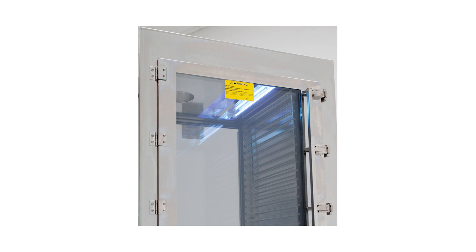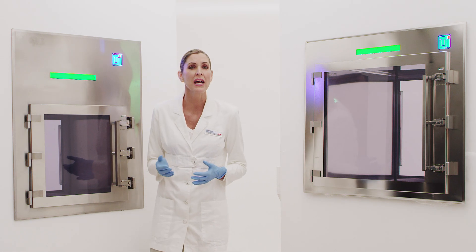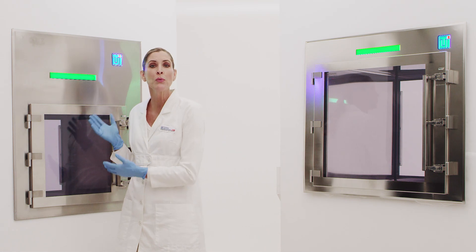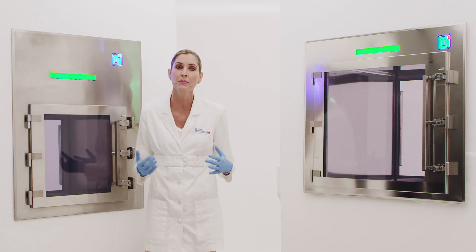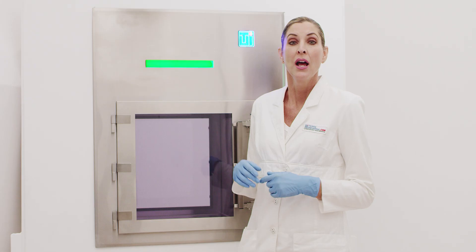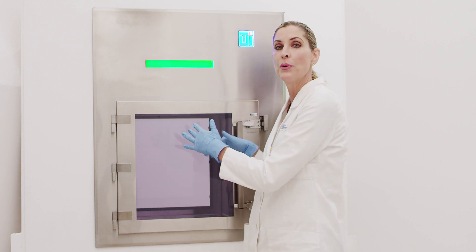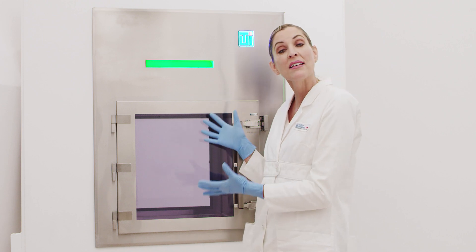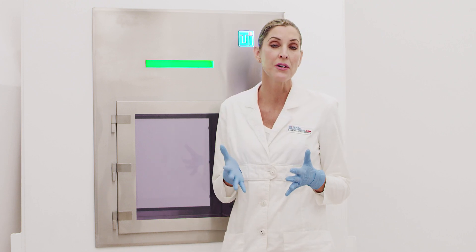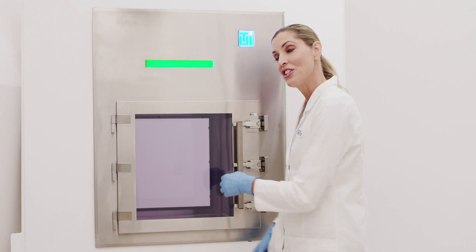The UV light automatically shuts off when either door is open to prevent accidental exposure. To reduce the risk of sample cross-contamination, Terra Universal Smart Pass-Through chambers can be equipped with recirculating HEPA or ULPA filtration systems that exceed USP 797 and 800 requirements. These closed-loop, self-contained systems run continuously to reduce particle concentrations within the internal chamber. Additional passive and active filtration options are available, including HEPA air showers and exhaust ventilation systems.